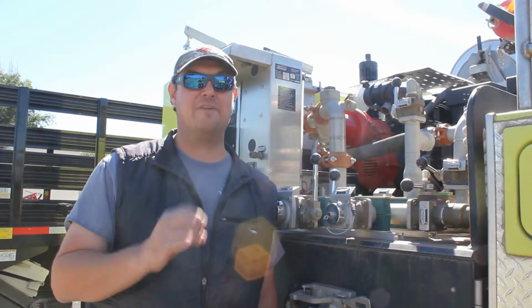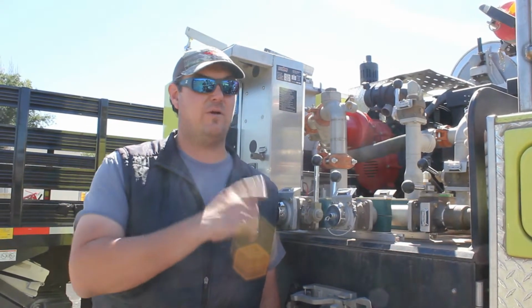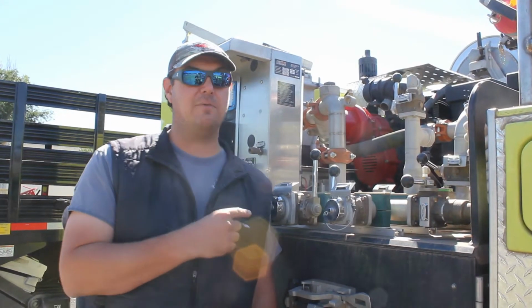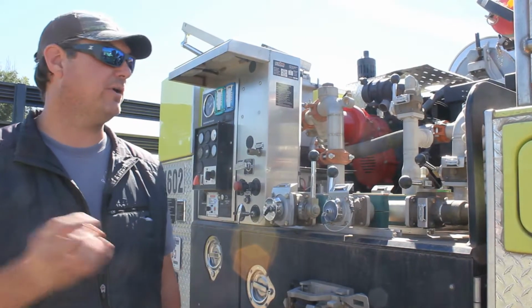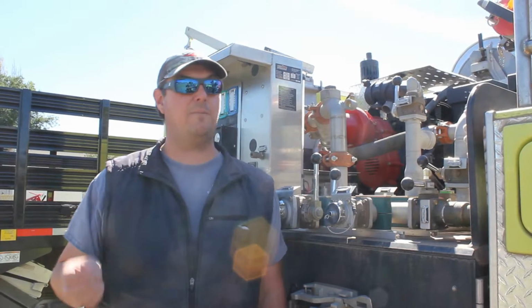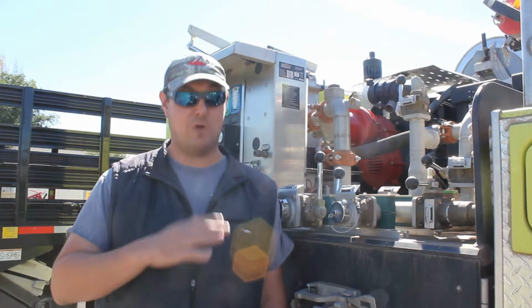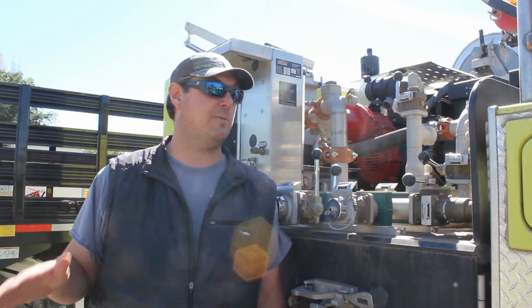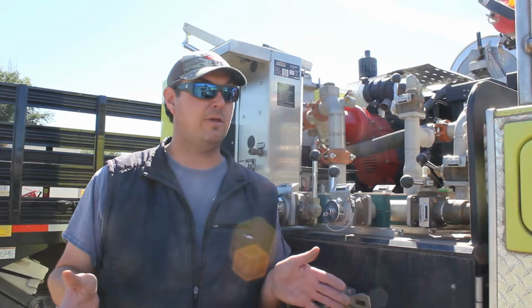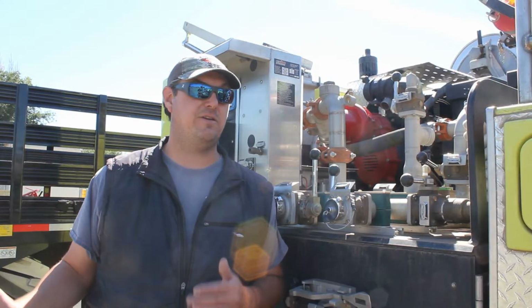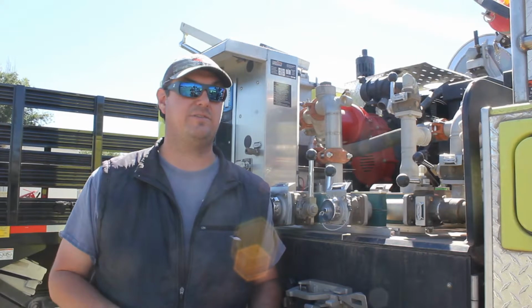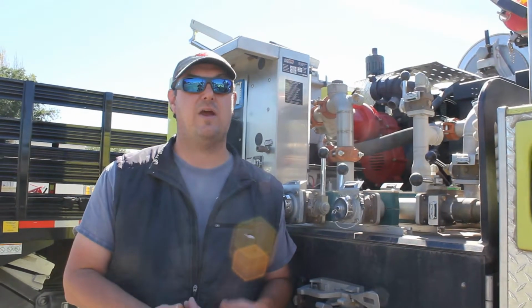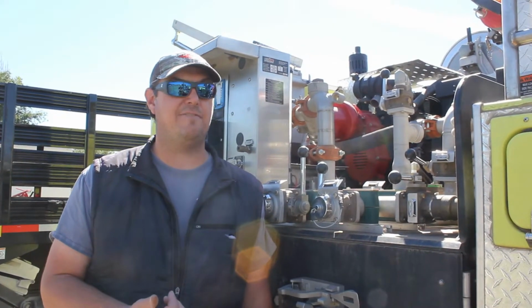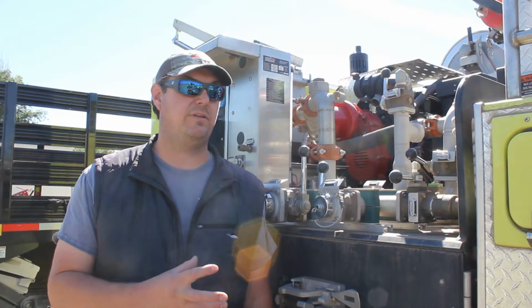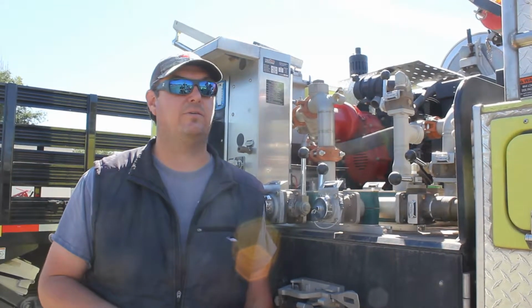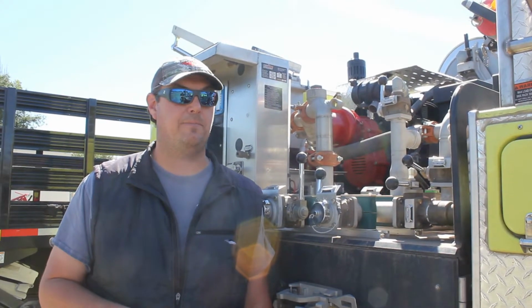Very important, never grease these. These all have a sealed bearing. If they come from the manufacturer with a grease zerk, put grease in them. But if they don't come from the manufacturer with a grease zerk, do not put grease in them. Same thing with a Mark III that comes from the pump shop, that comes from the cache system. If they don't have a grease zerk, don't put grease in them. That grease will degrade the graphite seal, and it'll eventually fail that seal. So keep grease out of them.